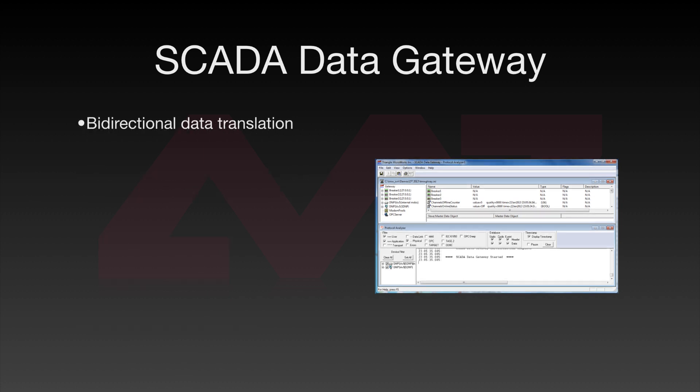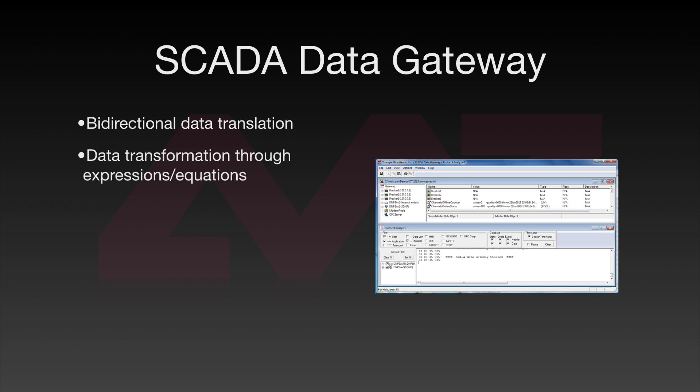The SCADA Data Gateway supports bi-directional data translation. For example, it can pass data from an outstation to a master as well as send commands from that master back to the outstation. It also supports expressions and equations to perform data transformation. For example, if a device reports integer values, the SCADA Data Gateway can scale those values and report them as floating point numbers in engineering units.